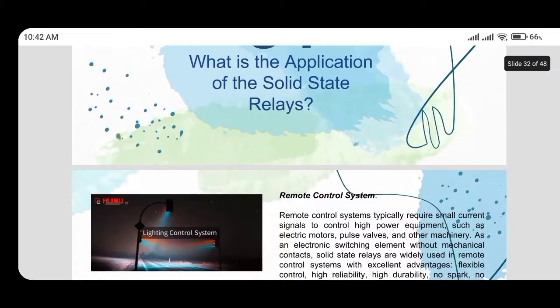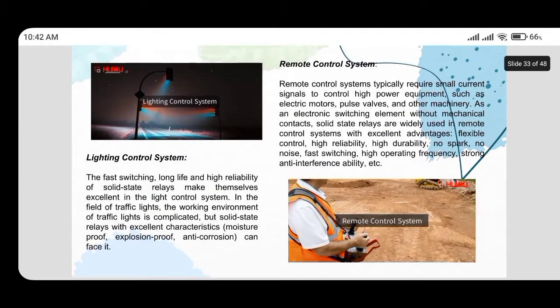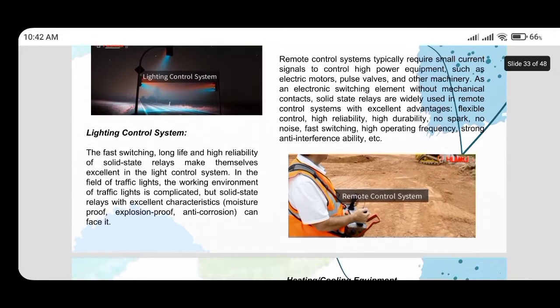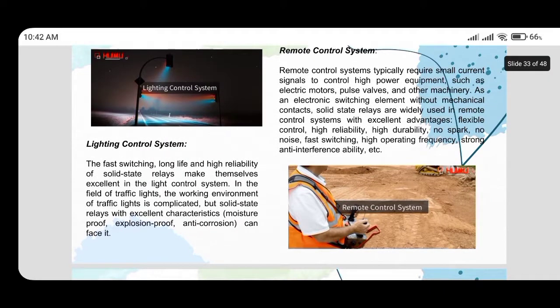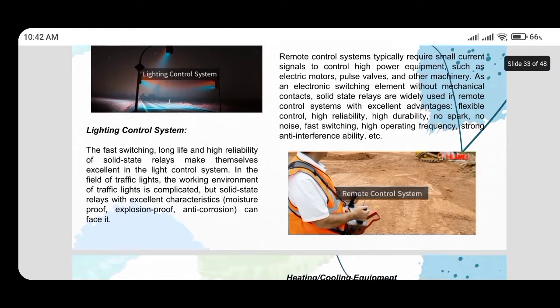Current signals can control high power equipment such as electric motors, pulse valves, and other machinery. As an electronic switching element without mechanical contacts, solid state relays are widely used in remote control systems with excellent advantages: flexible control, high reliability, high durability, no spark, no noise, fast switching, high operating frequency, strong anti-interference ability, and so on.